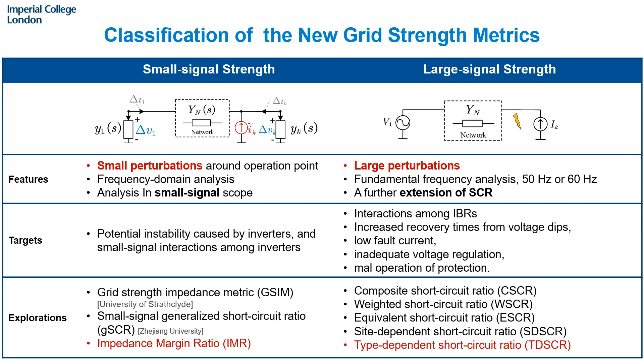Large signal strength aims to focus on system strength toward large perturbations, and it is analyzed at the fundamental frequency. It would be a further extension of the traditional SCR, but considering more. It considers interactions among IBRs, the increased recovery time from voltage dips, some low fault current conditions, inadequate voltage regulation, and maloperation of protection. There are already several existing methods in this area. I'm going to introduce them briefly later, and we are trying to propose something called the type-dependent short circuit ratio.